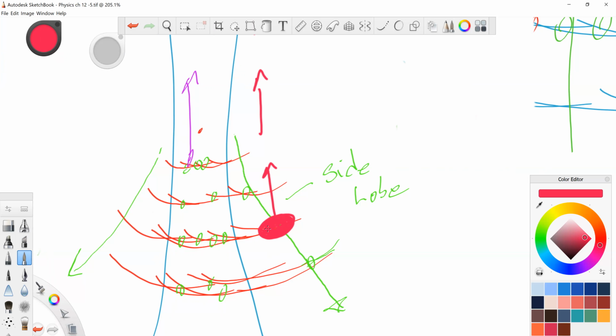it can't say, oh, that echo came from over there. It could only think that the echo came from here. Real, imaginary. So even though single element transducers produce side lobes, this is what you're dealing with. A lot of what you're dealing with on the screen when you ask why is it so fuzzy? Well, this is a big part of it.